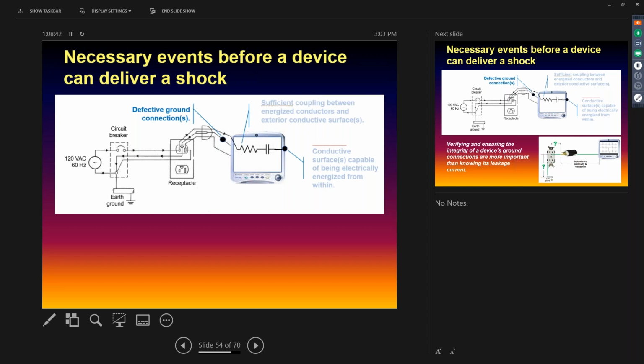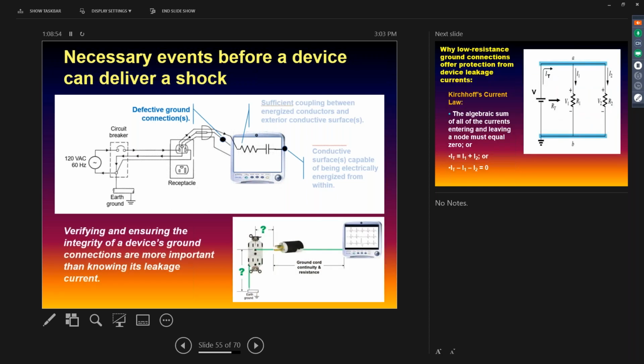So I just used that as my argument: I'm not doing that test because I've got a redundant ground in there, and it doesn't matter what the leakage current is if you have an intact ground. That's the third thing, defective ground.